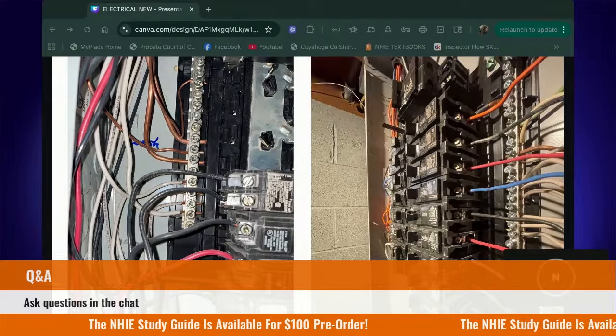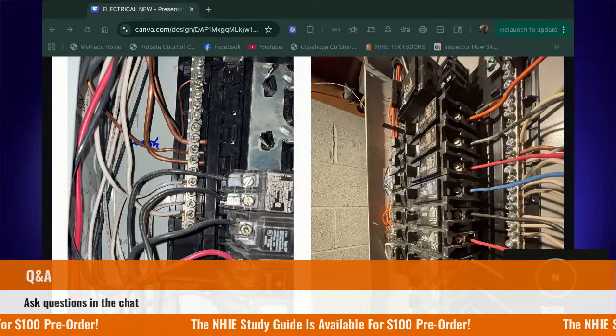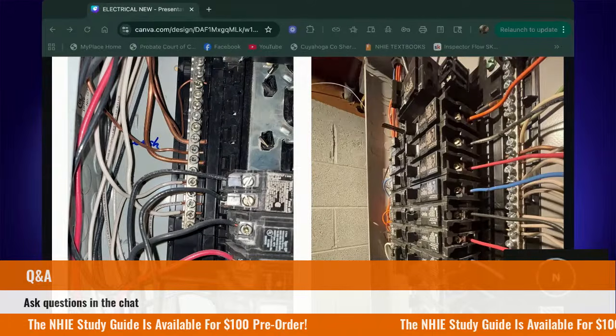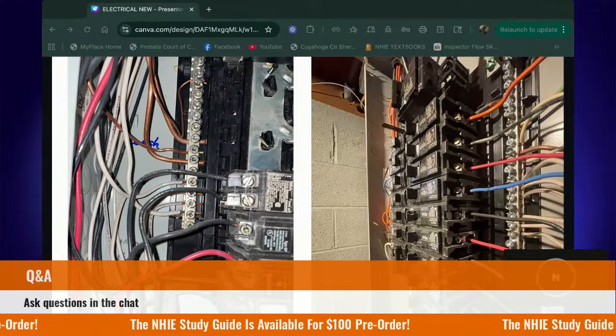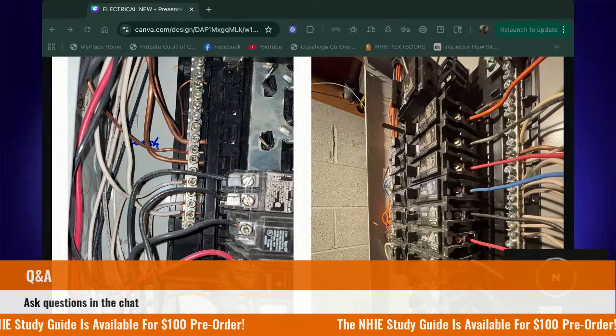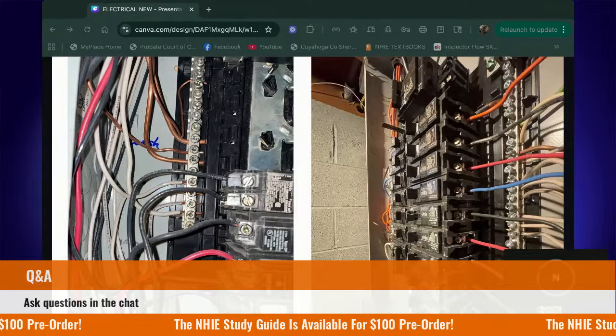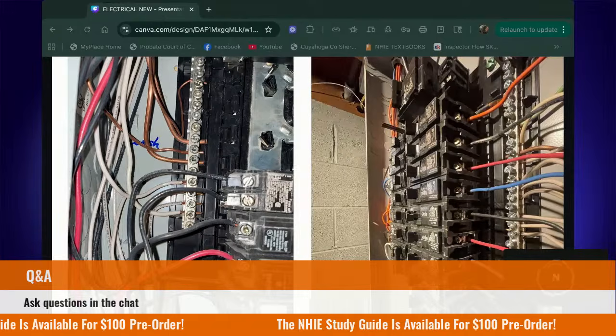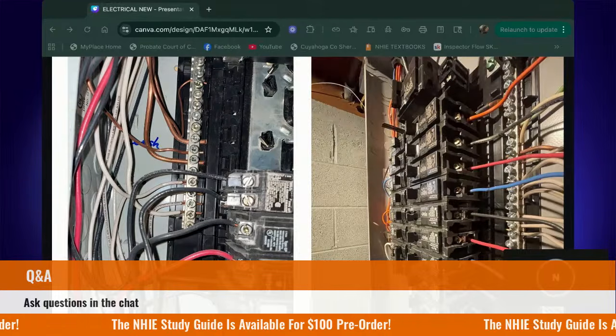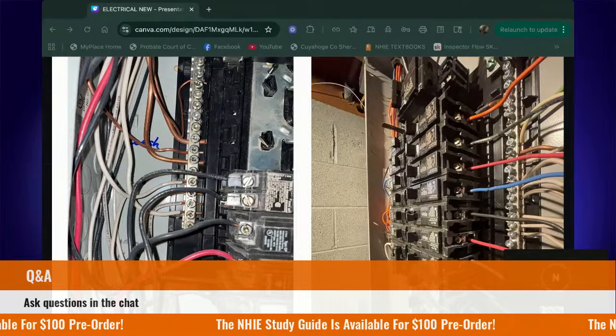So the grounding protects the electrical equipment, and the bonding is for protection for individuals. No, not quite. But let me get to grounding and bonding, and I'll put that all together for you. Right now, I want you to understand that the grounding system as a whole, your grounding wires, is a safety net. It's only in a worst case scenario, where there's a fault, that we will have current traveling on the ground. In a normal condition, when everything is okay, we will have current traveling on the hot and returning on the neutral. If for some reason a fault happens and we cannot return on the neutral, that's when the ground system steps in and says, hey, I've got a path directly to ground. You got it?